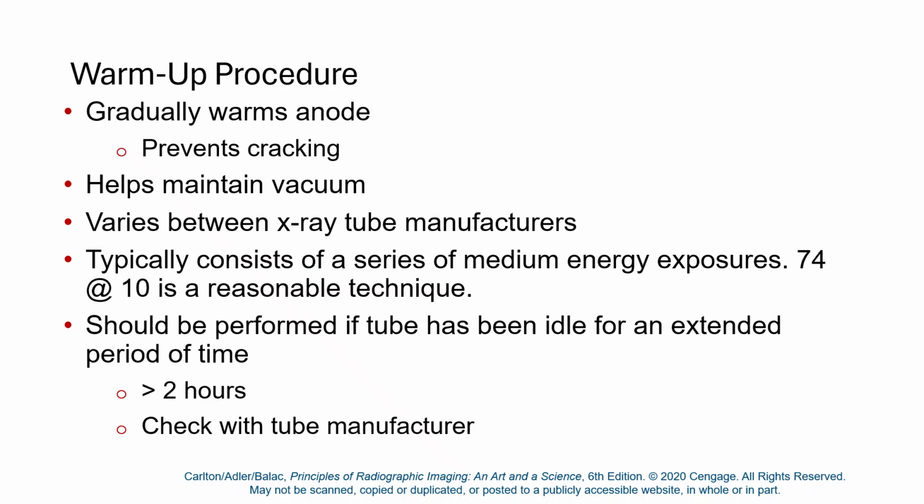Warm-up procedures vary, but a typical warm-up procedure is medium energy exposures, 74 kVp at 10 mAs, and do that like 5 or 6 times. If it doesn't have a preset warm-up protocol, that's a sufficient warm-up protocol.